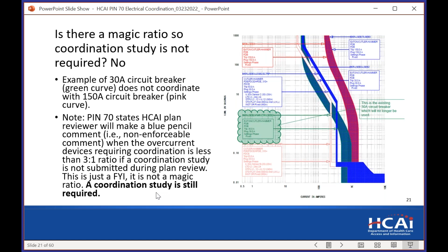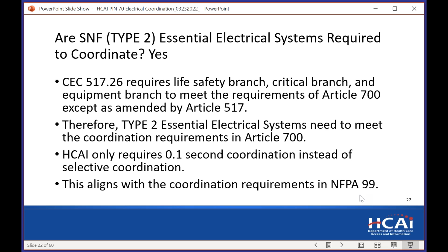Are SNFs required? And the answer is yes, and we talked about that. But the one thing we do at OSHPD is the SNF essential electrical systems are only required to coordinate from 0.1 second coordination instead of selective coordination. And we do this to align with NFPA 99, and it also just makes common sense that the requirement for a Type 2 should be the same as a Type 1 and not more strict than a Type 1.